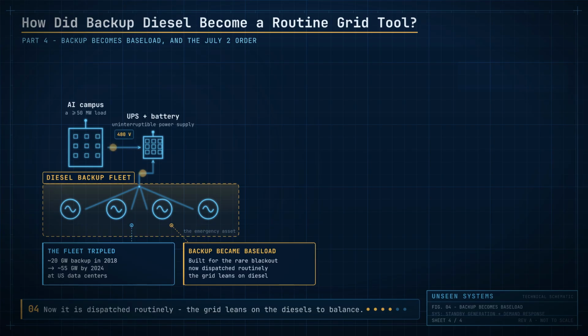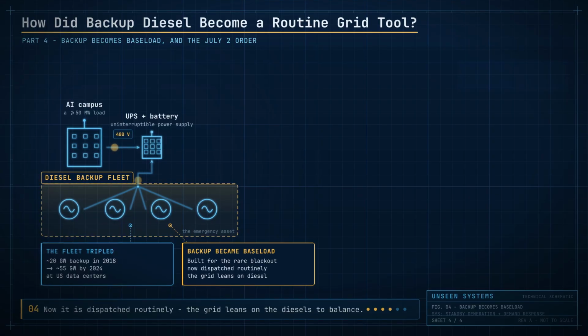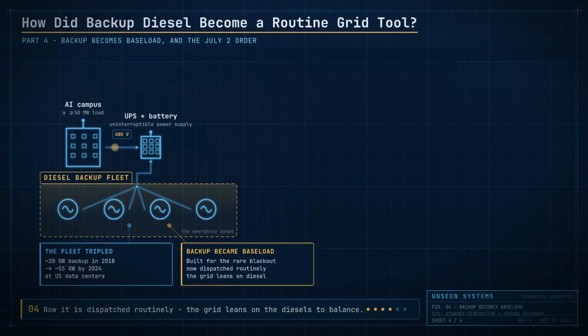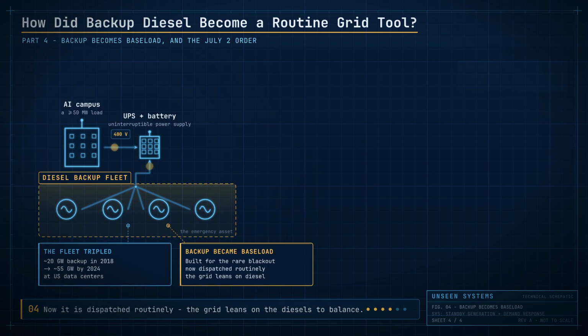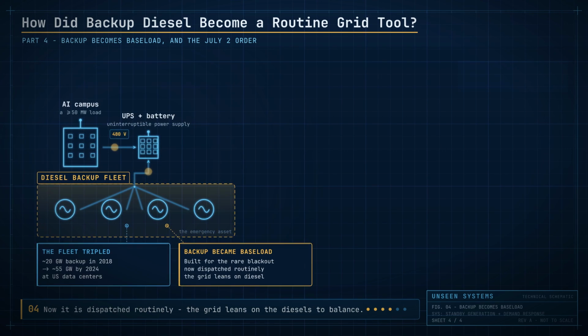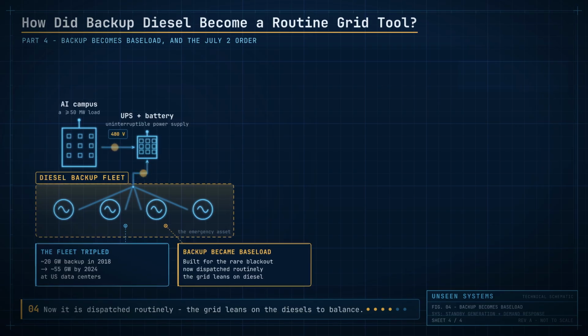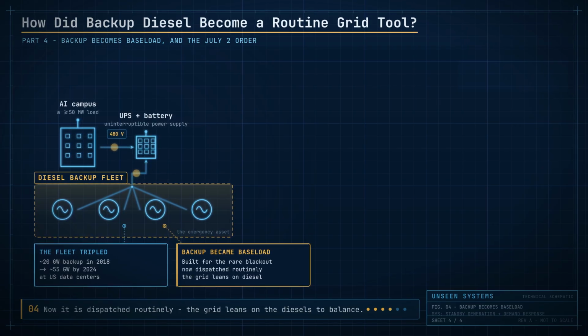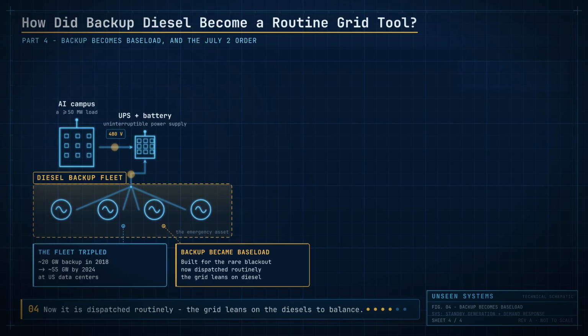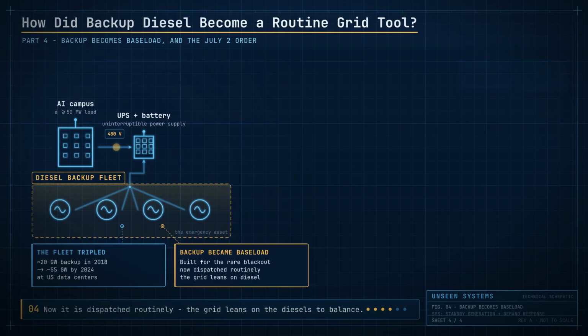And this genuinely surprised me. That backup is increasingly dispatched routinely as a balancing tool. When the grid is tight, operators fire the generators to shave what they pull from it, and to take part in demand response programs, running diesel not for a blackout, but on an ordinary strained afternoon. The insurance has quietly become part of the grid's own machinery.